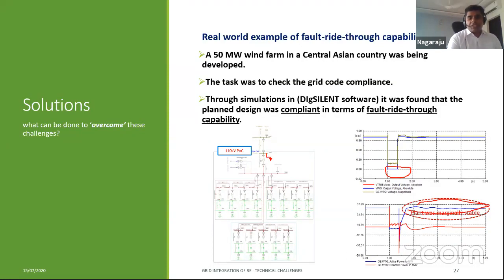This is the worst case scenario, when the grid is at its lowest fault level, very weak, and it happens maybe once in a lifetime. But the grid still requires that to be satisfied. They got an exemption and did not do any technical solution in this case. Otherwise, we would tell them to install either a supporting battery energy storage system, or an additional STATCOM, or go back and purchase different turbines.